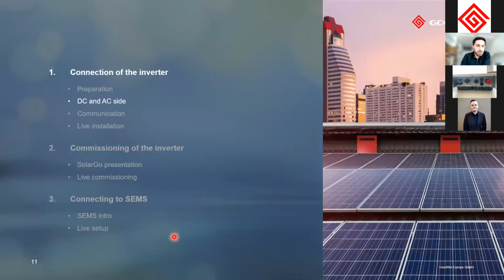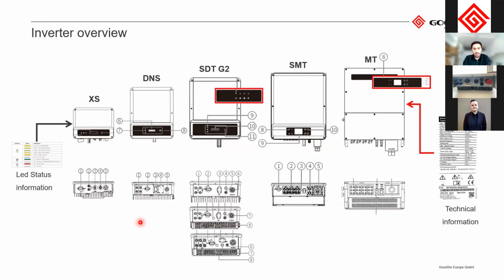Yes, and then when you're all prepared and the inverter is hanging on the wall, then it's time to install the DC and the AC side. Here's a quick overview of most of our grid tie inverters. As you see, they look quite similar on the front side, and then every connection is then done on the bottom side. There are a few different types.